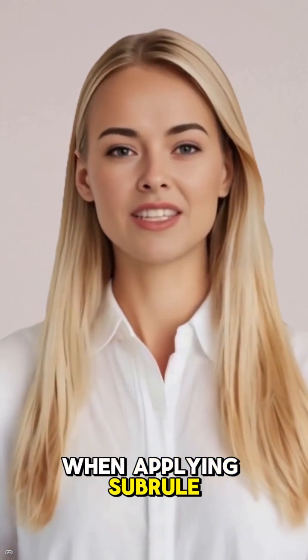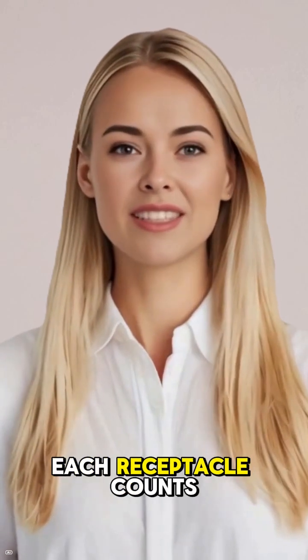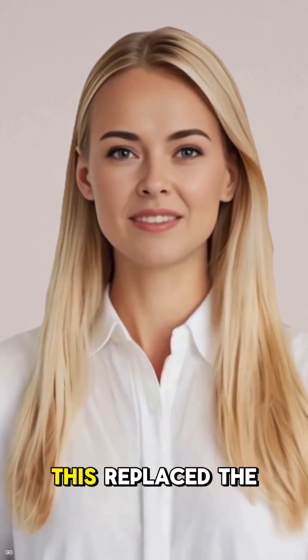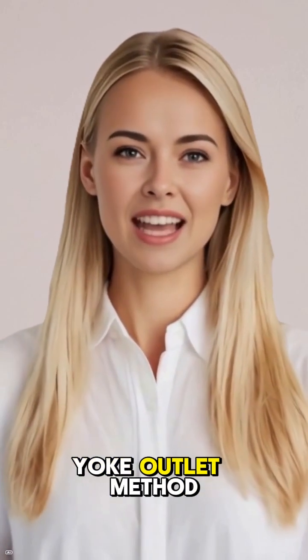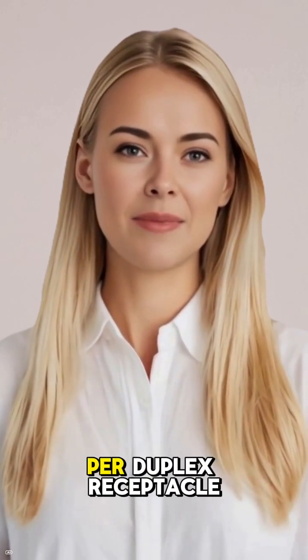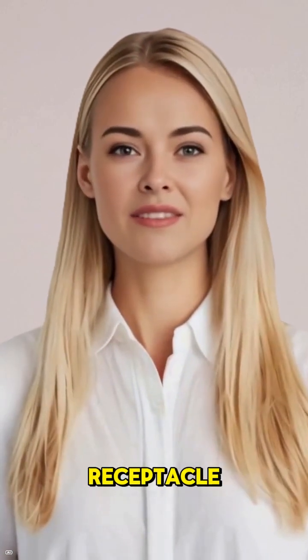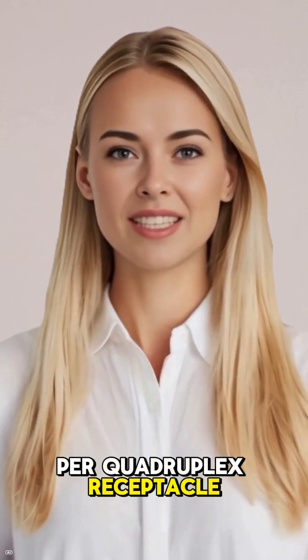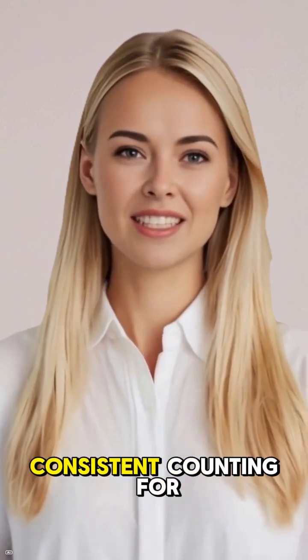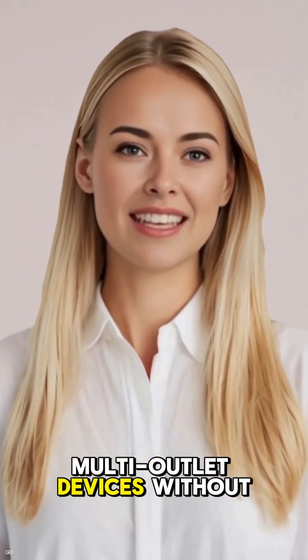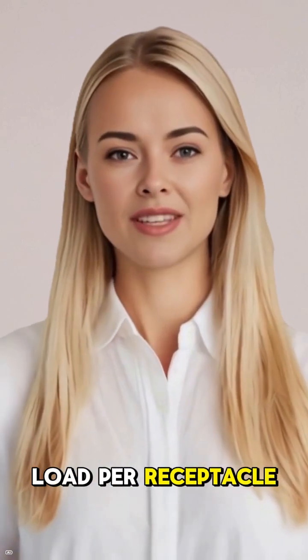Subrule 2, when applying Subrule 1 to receptacles, each receptacle counts as follows. This replaced the old 1 outlet per yoke method: 1 outlet per duplex receptacle, 1.5 outlets per triplex receptacle, 2 outlets per quadruplex receptacle. This provides clear, consistent counting for multi-outlet devices without needing to assume load per receptacle.